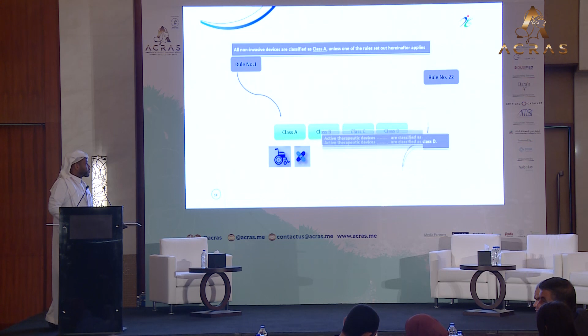Section number 2 is the information to be supplied by the manufacturer. Technical documentation shall include a full set of labels, the packaging, instructions for use, and any promotional material. This is very important to have, especially the promotional material. It should be provided in the Arabic language, and this is very important if the device is intended to be used by a layperson. This is a very important point.